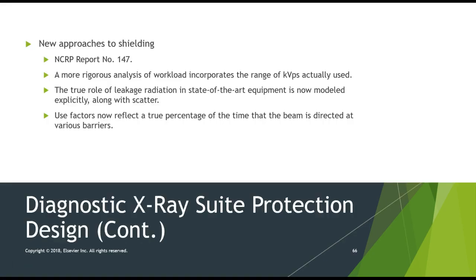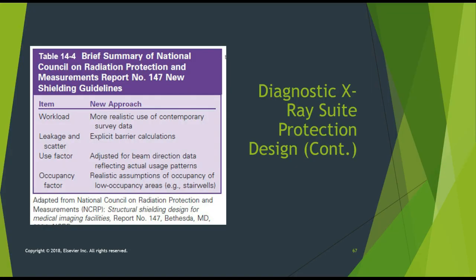Okay, there are new approaches to shielding and barrier calculations, and they are in NCRP report number 147. They're very rigorous. They use very finite, minute numbers, and so they're very precise. Okay, this again is a table on those factors. So workload, this is the new approach. Workload, they're using more realistic data. The leakage and the scatter, the explicit barrier calculations, they're down to however many decimal points, not anything that you need to remember for my test. The use factor has been adjusted for beam direction data to reflect actual usage patterns. I'm not sure how they get that data, but there you go. And the occupancy factor has realistic assumptions of occupancy versus just guessing who will be there and how many people in 1 week.